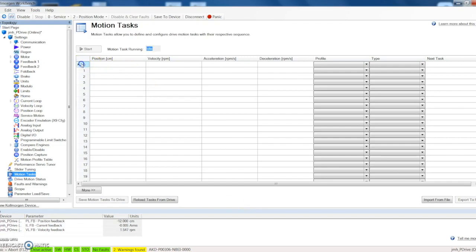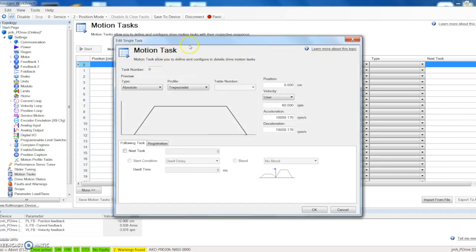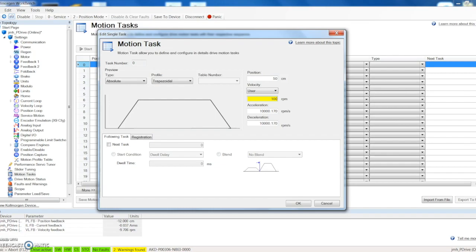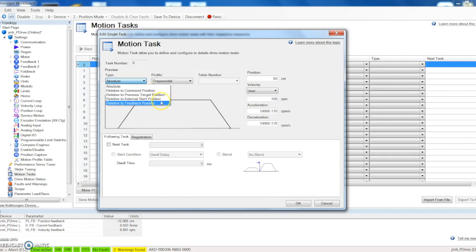Now here in motion tasks is what allows us to actually start programming some positions. So let's go ahead and do one. If you select to the right that selects the whole field. You can see our position is in centimeters, velocity is in RPM, so remember that. Now we can double click here, open up this motion task. We can call it moving centimeters. Now if we had an actuator out there and we knew that we wanted to stroke the actuator 50 centimeters, we could select 50, change our RPM let's say to 100, and we want to make sure that this is a trapezoidal type move. We are going to absolute position. We could change our position type to relative position, but we want an absolute position on this move. We know we are going to 50 centimeters out.